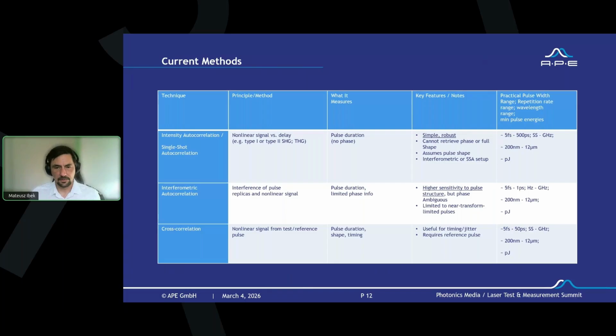It only measures the pulse duration, but it is very simple and robust. Since it only measures the pulse duration, it cannot retrieve phase or full shape. We have to assume the shape in this case, because the autocorrelation is a convolution of two pulse replicas, and through fitting it has to be guessed how long the pulse was. The better the fitting, the better the guess of the pulse duration.